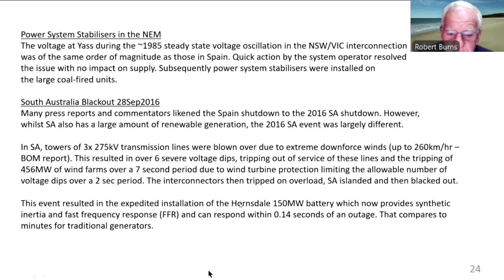In South Australia's case, they expedited the installation of the Hornsdale 150 megawatt battery. Well, it was 100 initially, now it's 150. And it also provides synthetic inertia, fast frequency response. And so it's quite good for when you do lose a generator. And of course, that's even quicker than some of the conventional generators.